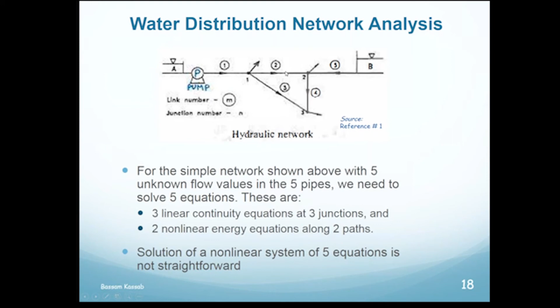I'm going to show in the next slide how it looks. The head of the pump is related to the difference in elevation between the reservoirs, and you add to it the friction loss and the minor loss, because the pump has to overcome all of that, friction loss and minor loss, in addition to the elevation between the reservoirs. Back to this - that's Z1 minus Z2 or Z2 minus Z1, it's called the static lift. The pump has to overcome that and all the losses. So that's the system curve, based on the equation I just showed you. I'm going to flip to that now in a second - that's a parabola, a branch of a parabola here.